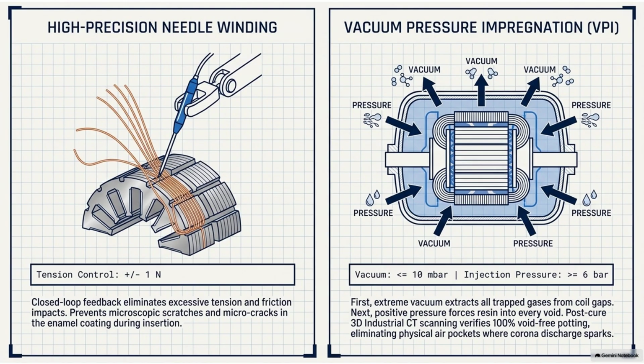But even with nanotech wires and Nomex fortresses, you are still letting that brutal series voltage spike hit the motor. The root cause is still there. Remember that brutal 10 kV per microsecond voltage slap from the SiC inverter? If we can't change the inverter because we need the efficiency, how do we protect the motor? By physically altering the shape of the electrical wave before it arrives. Engineers implement an optimized high-frequency LC filter, or a common mode magnetic ring, at the inverter output. Okay, let's break down the LC filter physics. That's an inductor, L, and a capacitor, C. How do they reshape the wave?